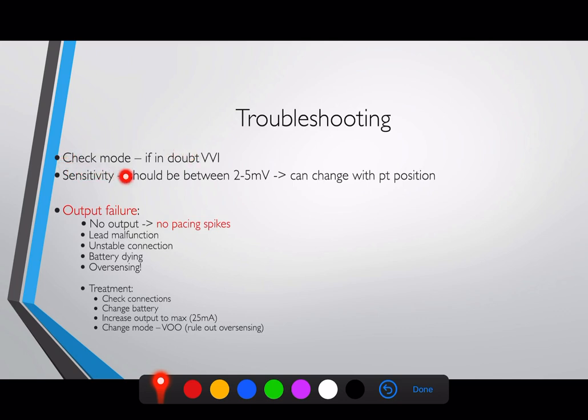Check your settings — these should be documented every ward round: what the threshold voltage was, the rate, and the sensing millivoltage. If settings have changed, change them back. If they haven't changed, consider whether the box itself has failed intrinsically and needs replacing. Also check the mode — if ever in doubt with temporary pacing wires, put it into VVI.